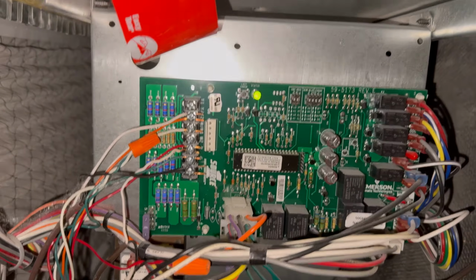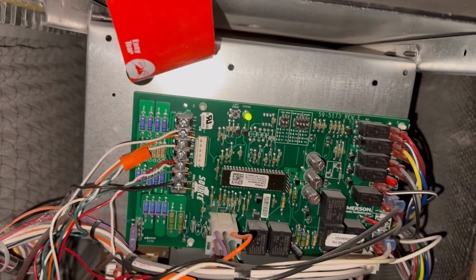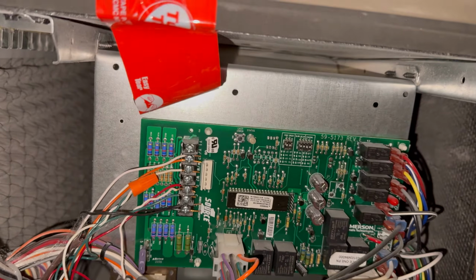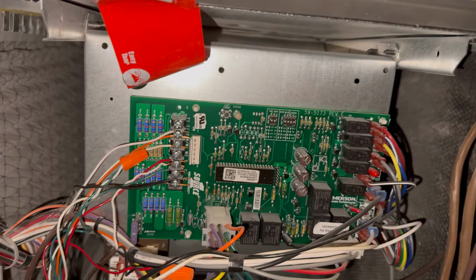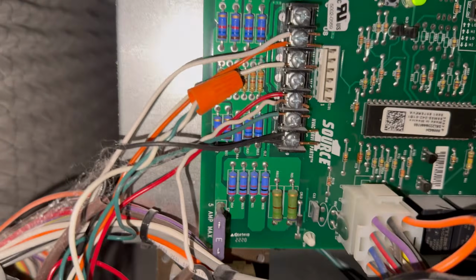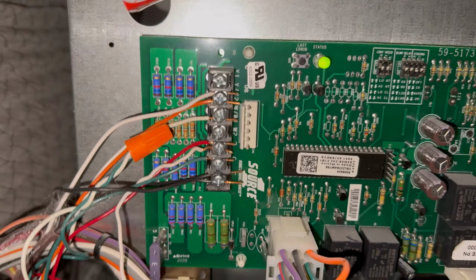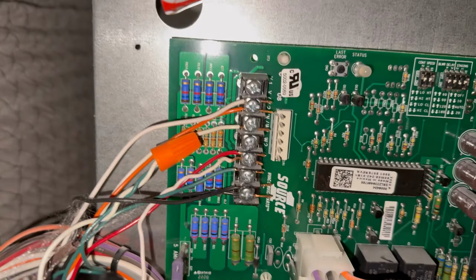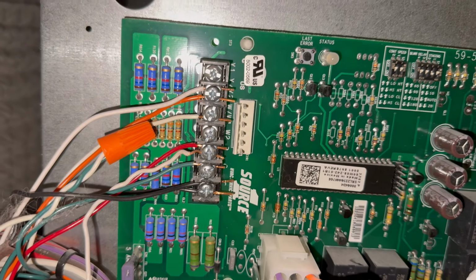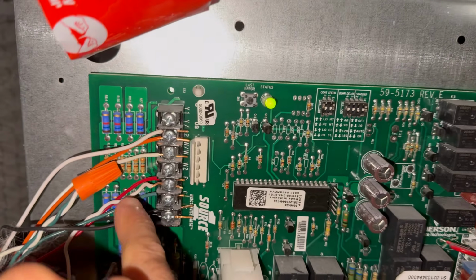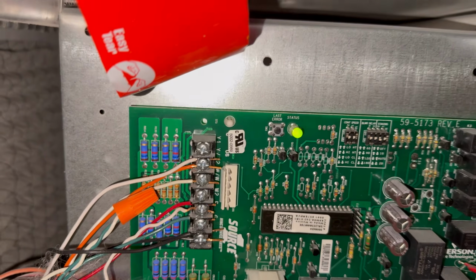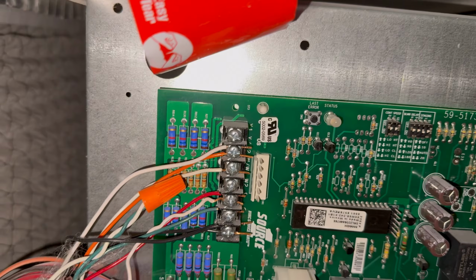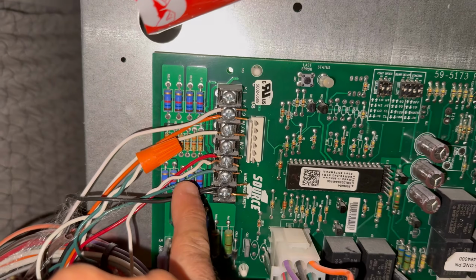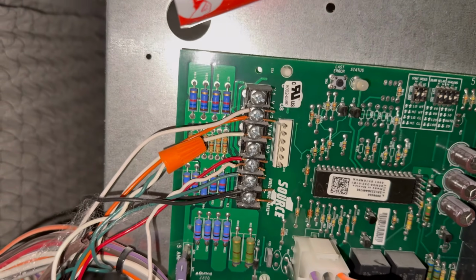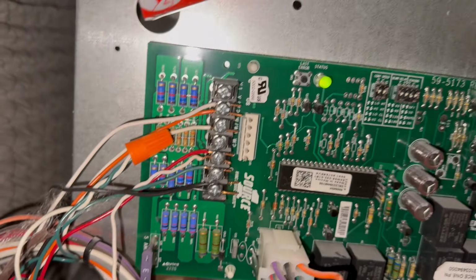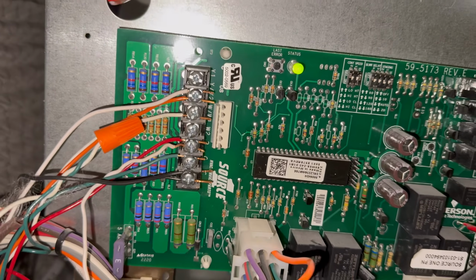This is the furnace control board. Yours may not look like mine because you probably have a different furnace entirely. But there are two different boards that I need to talk to you about. The first is, of course, the one that we're looking at. In my case, you'll see here you have these terminals, and they're all labeled Y, W, G, R, C. What we're going to connect is the two wires from our pressure switch. One wire is going to connect to the C terminal. The other wire is going to connect to our W terminal, where there's currently a white wire going in. Black wire goes to C, and the white wire goes to W. You're going to connect your two wires from the pressure switch and put them here. And then you can get rid of your pressure switch altogether.